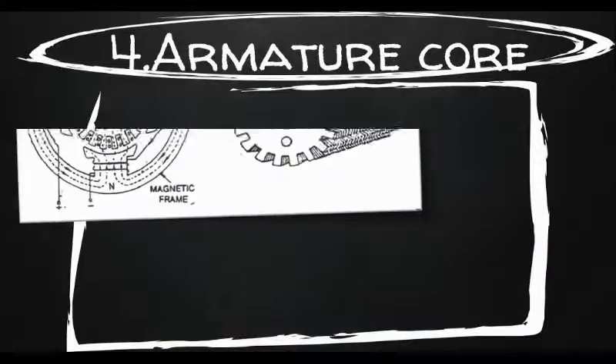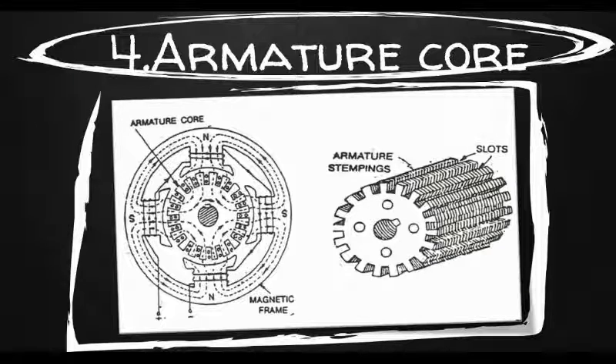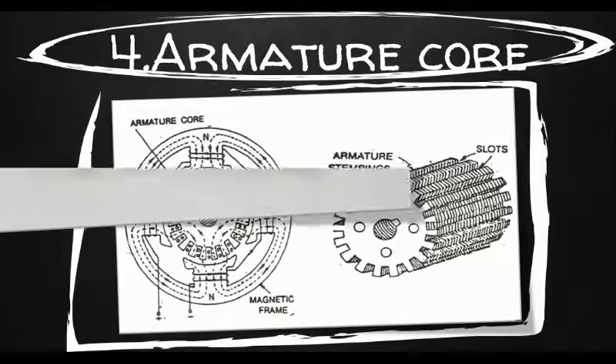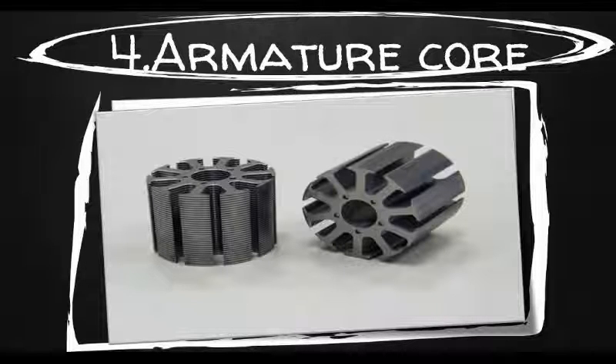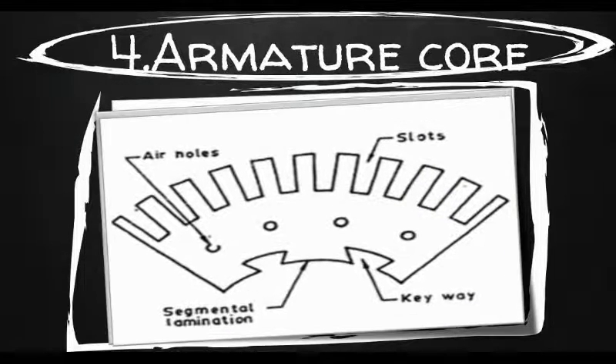Armature core: It houses the armature conductors or coils and causes them to rotate, and hence cuts the magnetic flux of the field magnets. Its most important function is to provide a path of very low reluctance to the flux through the armature from a north pole to a south pole, as you can see in the figure. It is cylindrical or drum shaped and is built up of circular steel discs or laminations, and is keyed to the shaft. These laminations are perforated for air ducts which permit axial flow of air through the armature for cooling purposes. Such ventilating channels are clearly visible in the laminations in the figure, shown by the air holes.